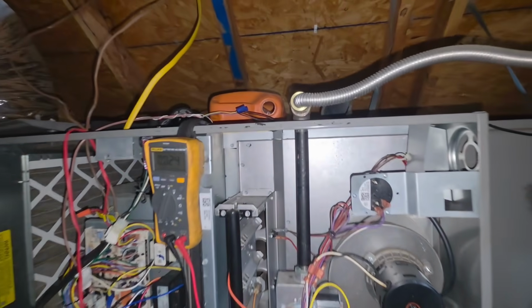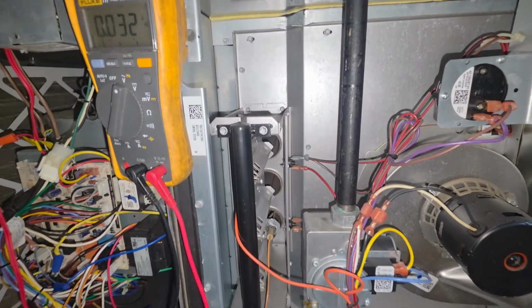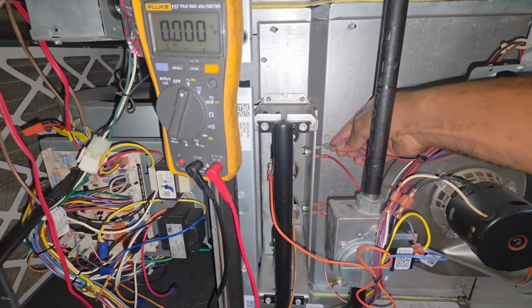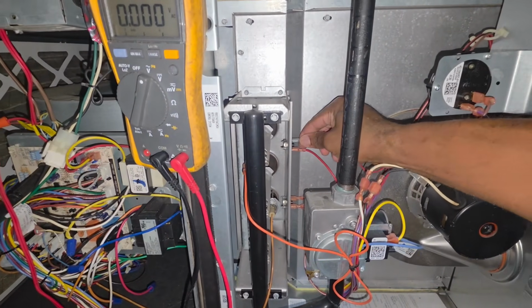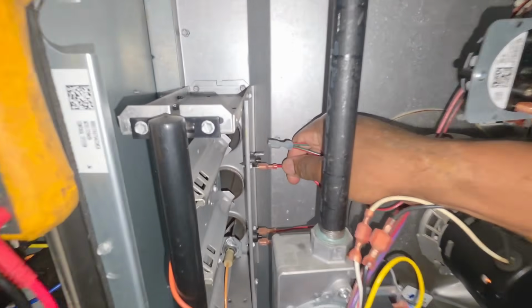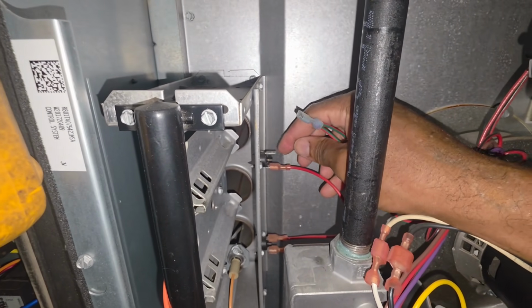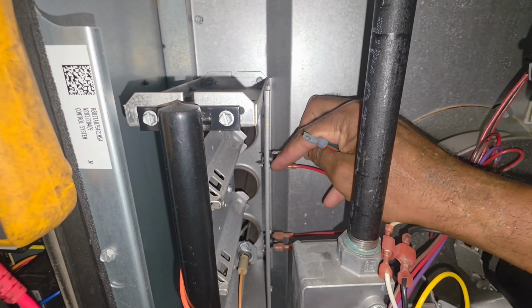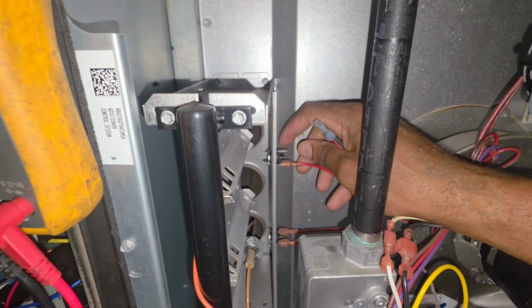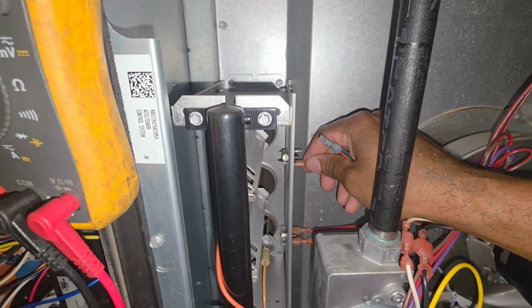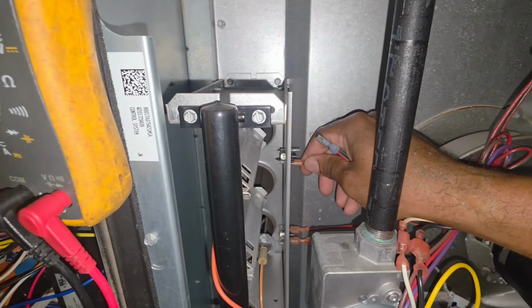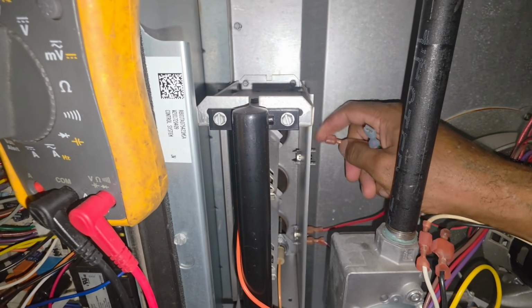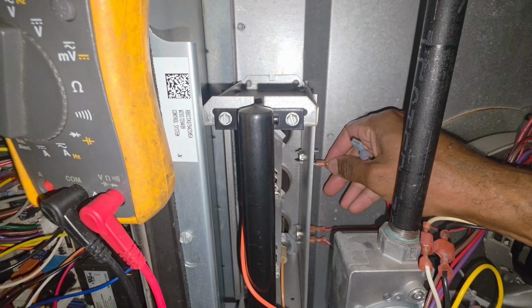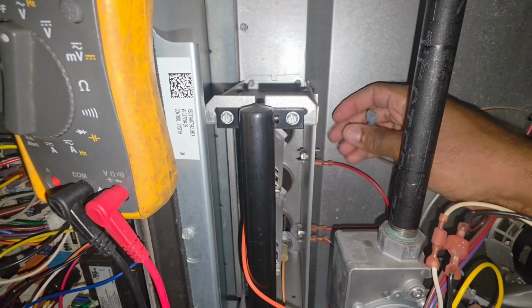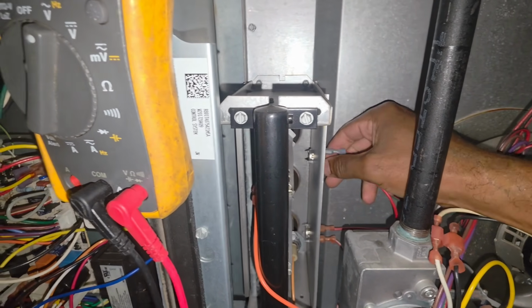All right, so right now I got the system off. There's no power to the unit, but I just want to show you some of the components, how they look in here. Like I say, you need to get familiar with what's inside your unit. These are limit switches right here. This is what we check in the terminals. Like I say, we have to check this live. If we were checking this with no power to the unit, we can check continuity and see if this switch is open or closed. But with the pivot method, we can do it with the unit when it has power to it.